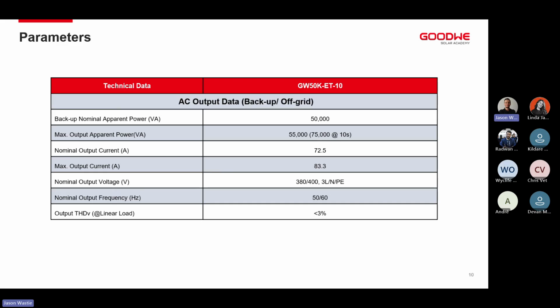And then one of the next features of our inverter, if we look at the max output apparent power, it's 75 kVA, 75 kilowatts for up to 10 seconds is what we can handle for inductive load startups and things like that, or any overloading purposes. So how our inverters work when it comes to overloading is, yes, we are high frequency transformerless inverters. However, for overloading purposes, we use the built-in DC capacitor bank that's built into the inverters, meaning that if there is any inductive load startup or heavy load startup or anything that exceeds the 55 kilowatts, we can handle up to 75 kilowatts for 10 seconds.